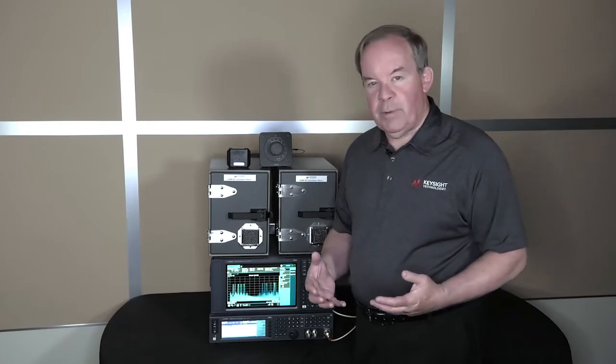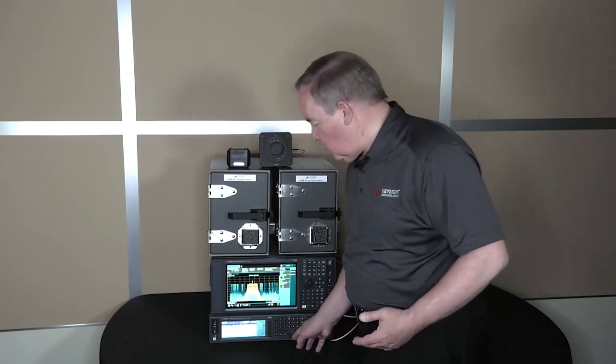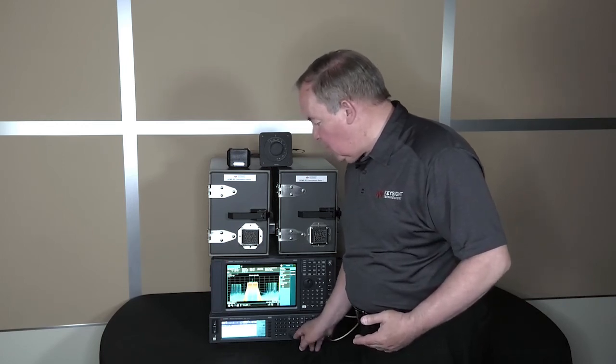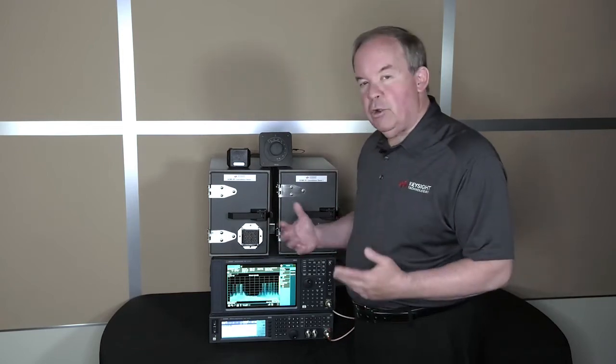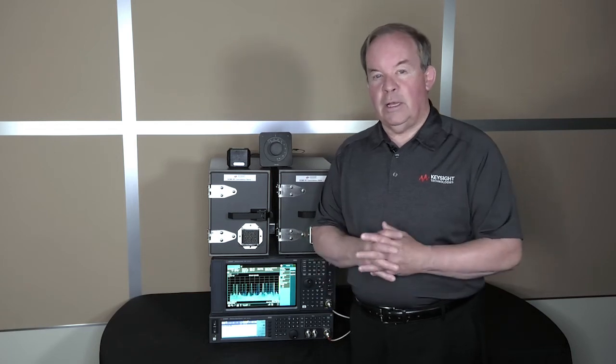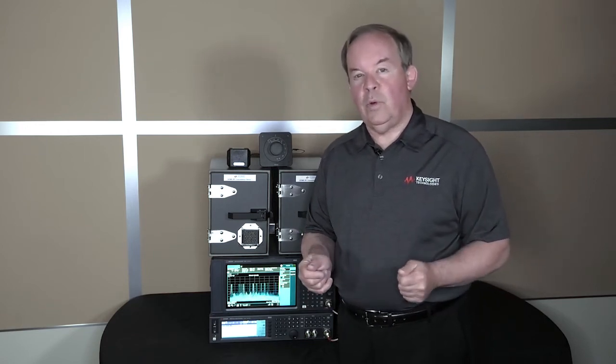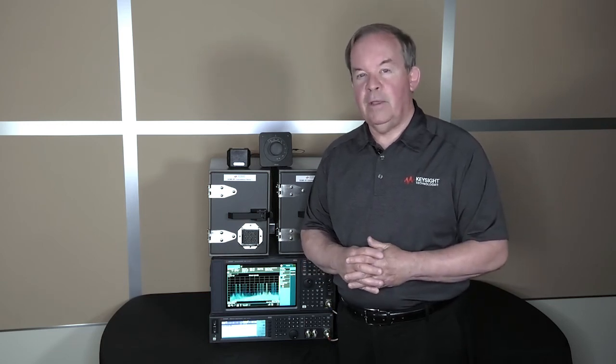It remains an absent area on the spectrum, but an even stronger signal can completely take out that wireless connection. At some point, we'll actually lose the connection between the speaker and the DUT. So this is the kind of wireless coexistence testing that's becoming necessary today. Again, it's defined by ANSI standard C6327. For medical devices, check also the AAMI TIR69, which focuses on healthcare devices where risk is an important consideration. What signals, what amplitudes, what densities of signals must your device be able to cope with, or at least to specify what that device can do? So I hope you've learned a bit about C6327, the kind of instruments that Keysight offers to help you make this measurement in a very useful way that can make your device more robust in its target environment. Thanks very much for watching.